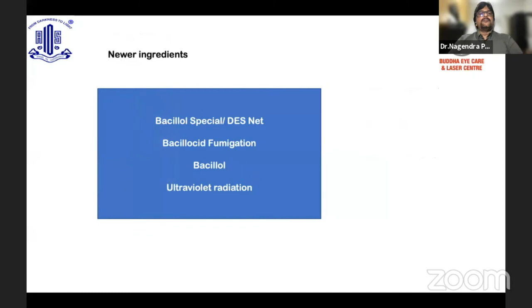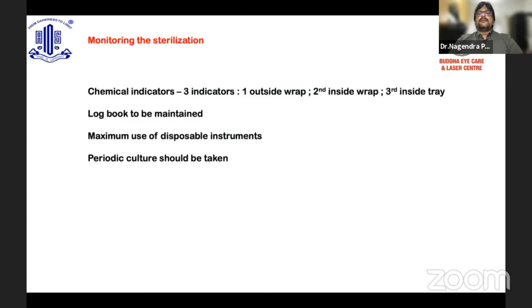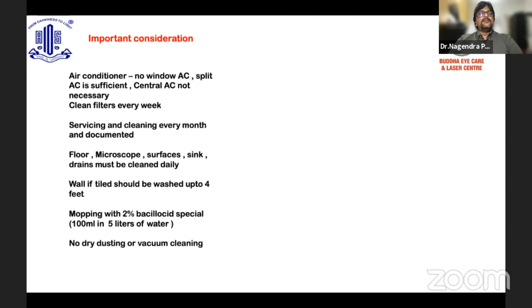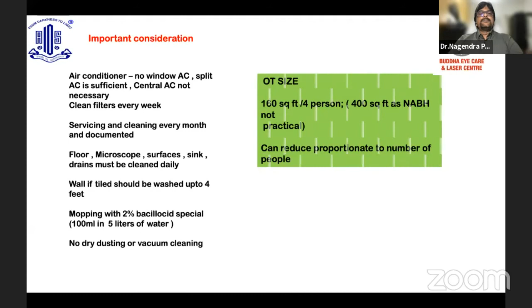Monitoring of sterilization is important by using 3 indicators: one outside the wrap, the second inside the wrap, and the third inside the tray. A logbook is to be maintained. Now, an important consideration: the AC should be cleaned every day and monthly, and there is no scope for window AC. Servicing and cleaning every month should be documented.